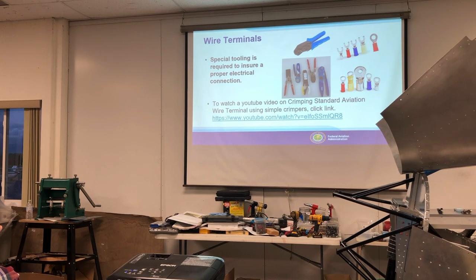You start out with circular little wires or strands. When you crimp, the forces are hard enough that it squeezes those conductors so the round shape goes away and all the air between the conductors is removed. That's how it prevents corrosion inside, and it cold welds the copper to the terminal.